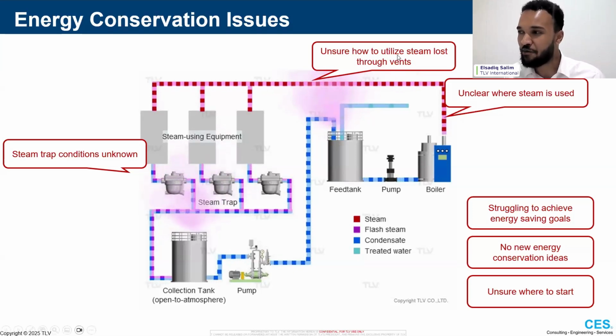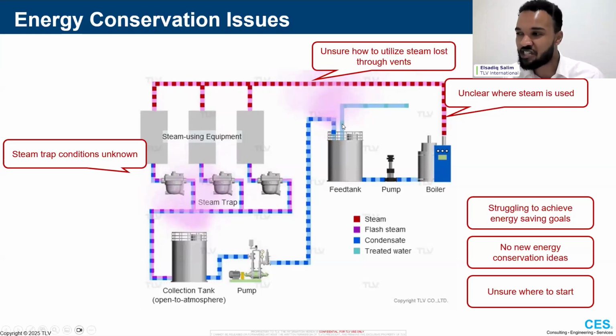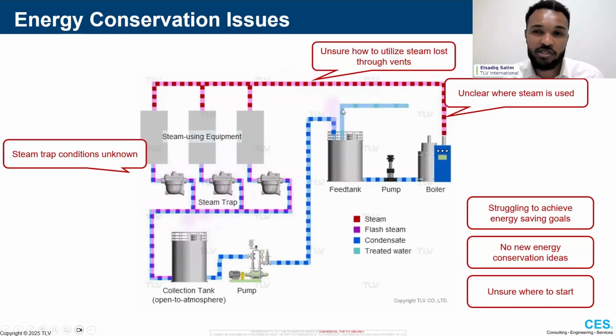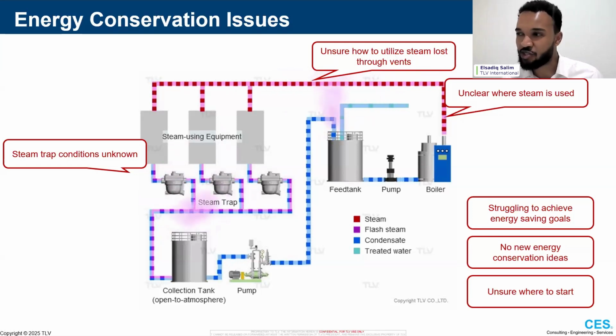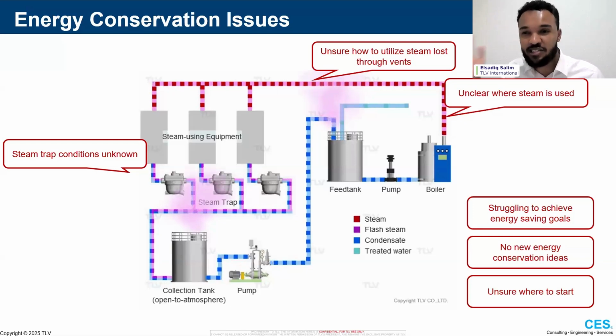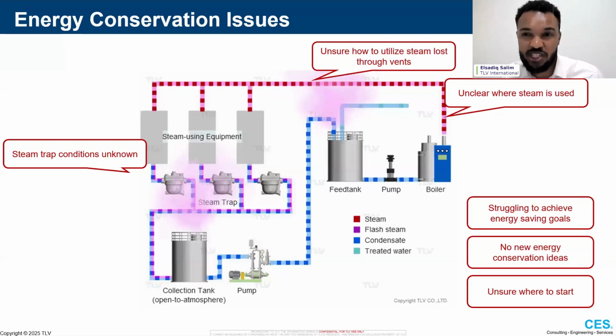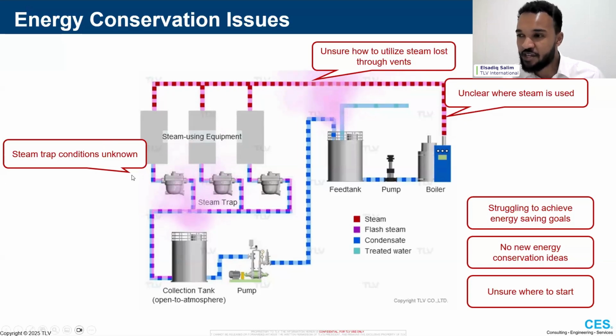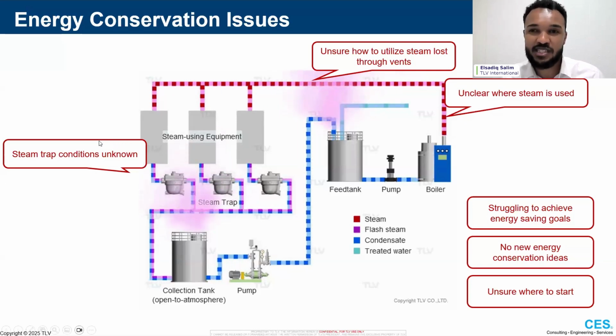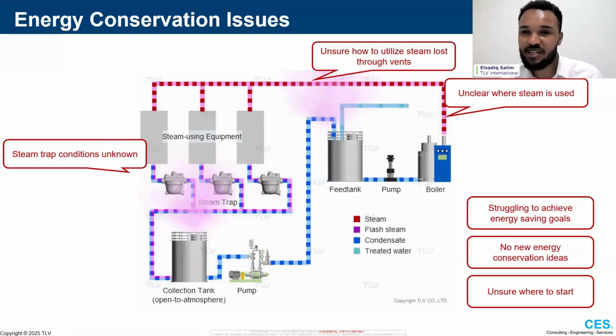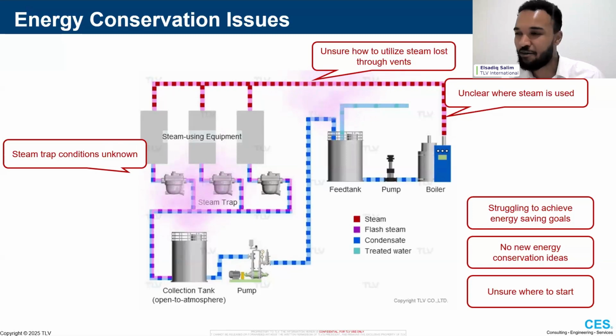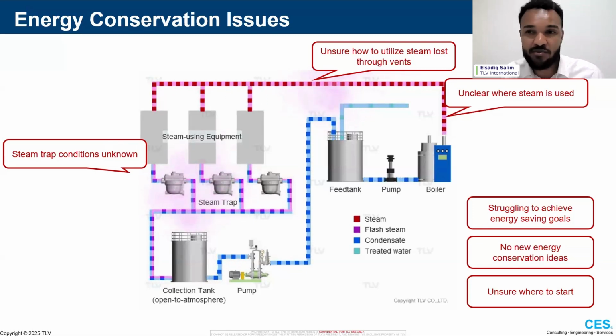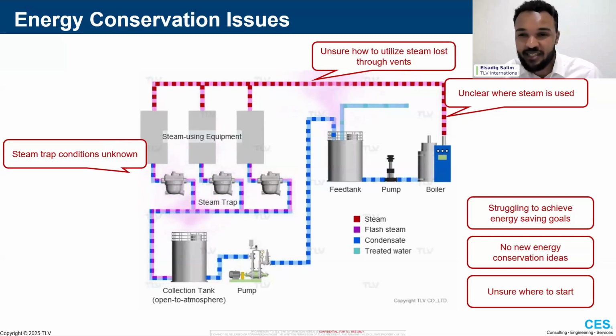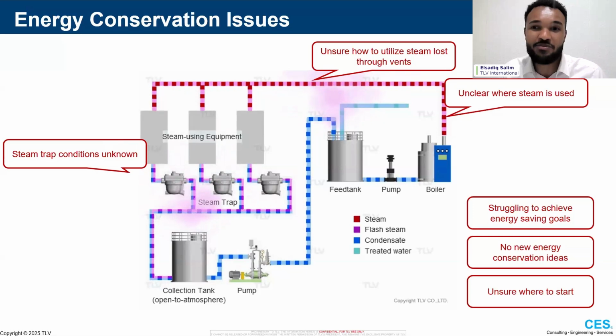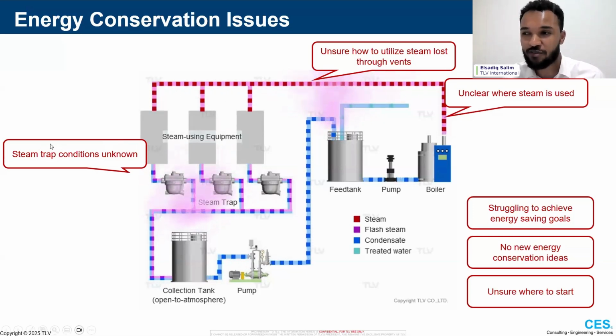Very common situation. And beyond that as well, engineers and non-engineers on site can see steam vents coming out of maybe condensate return tanks, boiler blowdown tanks, and they're unsure. They know that that's energy essentially going out the drain, energy being lost to the air, but they're unsure, how can we capture that energy? How can we reintegrate that flash steam and that energy back into our system? Then third point that's also very common is the steam trap conditions. Sites can have 200, 300, 400, sometimes 10,000 steam traps on site. But very commonly as well, they're unsure, what's the condition of our steam traps? How much does a working steam trap leak? Because actually it's true, working steam traps also pass some steam as well. So how much is that costing us? And it's not often known.